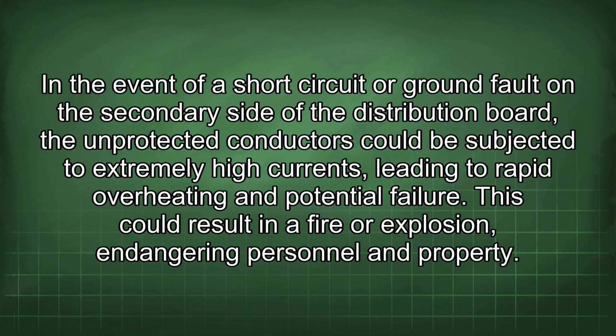In the event of a short circuit or ground fault on the secondary side of the distribution board, the unprotected conductors could be subjected to extremely high currents, leading to rapid overheating and potential failure. This could result in a fire or explosion, endangering personnel and property.